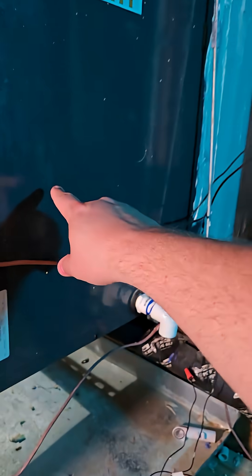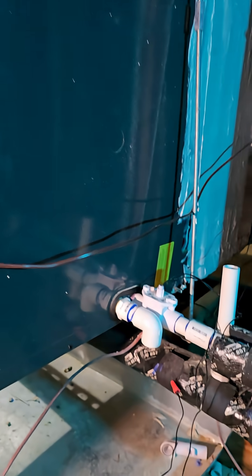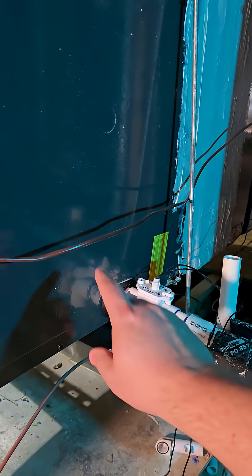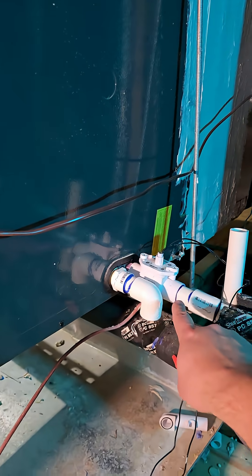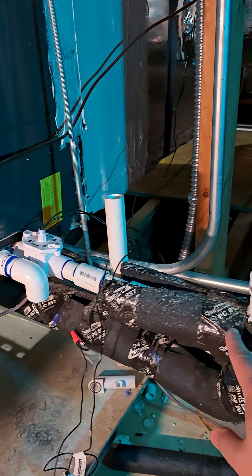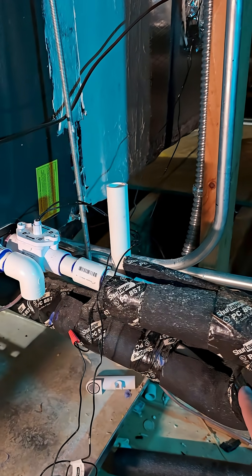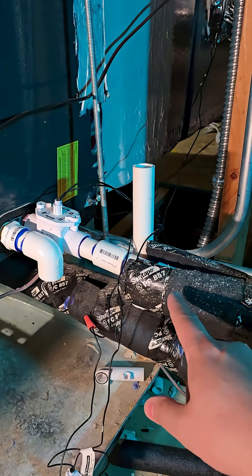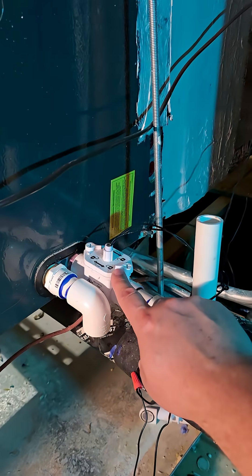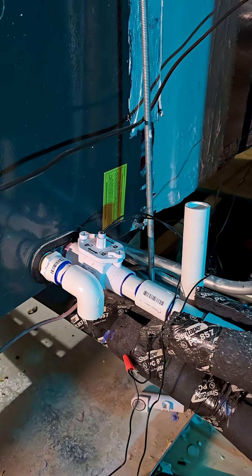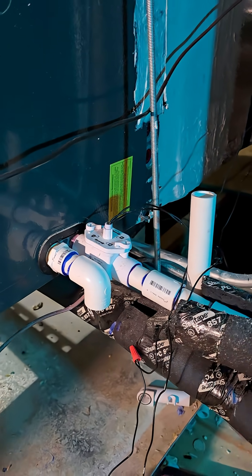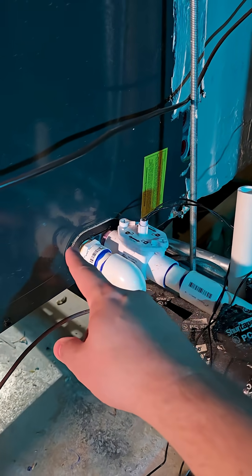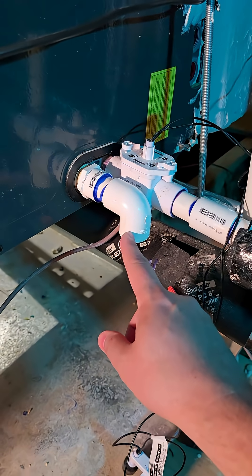Your air conditioning system pulls moisture out of the air and then it condenses and runs down these pipes either outside or into your plumbing drain system. If some of the pipes get blocked, then the water will back up into the system and flow out of the pipe here.